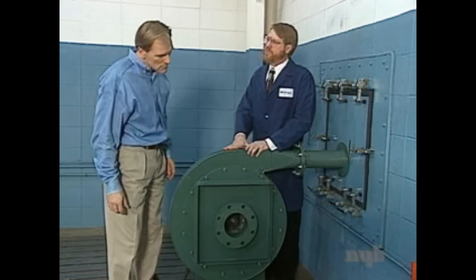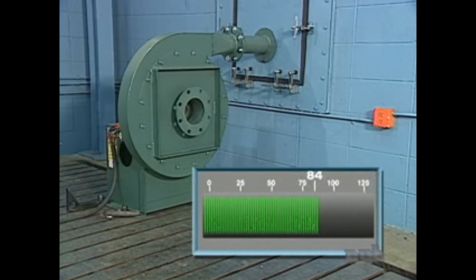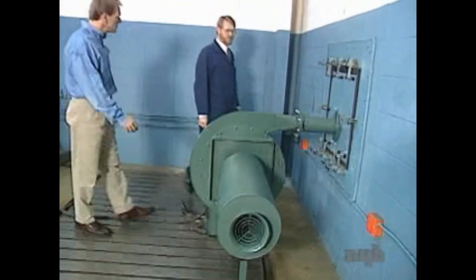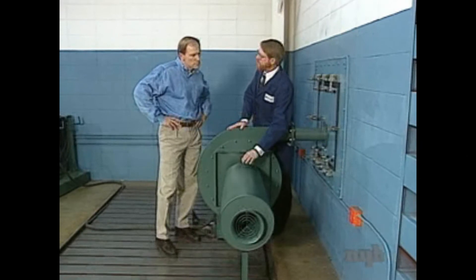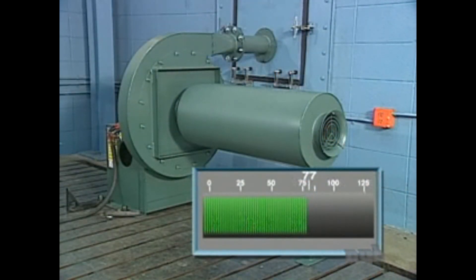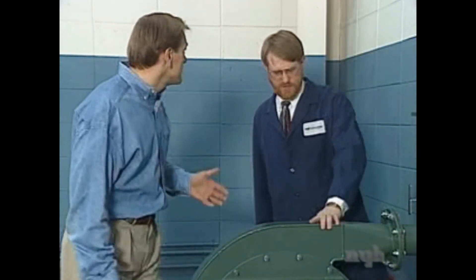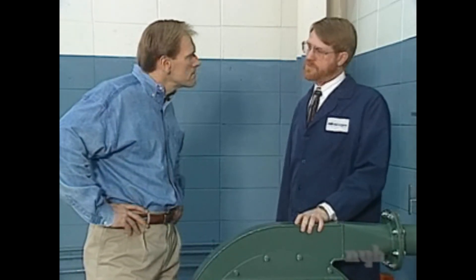Conversely, fan sound levels can be reduced with sound enclosures or silencers. Here's a pressure blower with an open inlet — let's note the sound level. Now here's the same fan with a silencer mounted on the inlet. Let's take a listen. Wow, you can really hear the difference. Silencers are a very economical method of significantly reducing the noise level at the inlet of a fan.